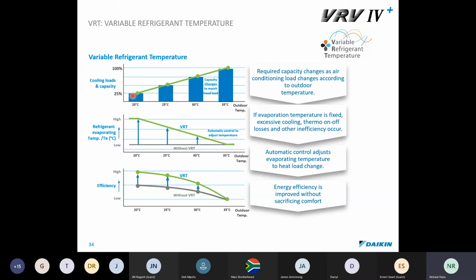That's basically your VRT, explained on a graph: at 35 degrees is what the unit is designed for, which is almost 100% of the load. Then as the temperature drops during the day, let's say to about 30 degrees, you are at maybe 75 or 70% efficiency. You have changes on the system, because if the evaporation temperature is fixed, think about it, you're going to excessively cool the space and get that dump of cold air. When you walk in, sometimes you have your aircon set at 23, but it feels like 20 degrees in the office. You get cold feet. This is all a result of overcooling.